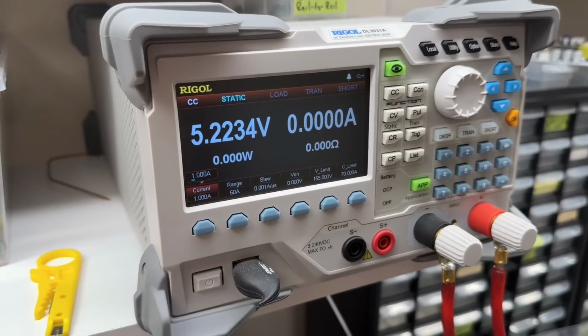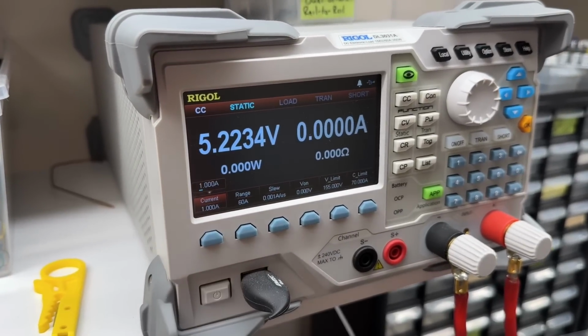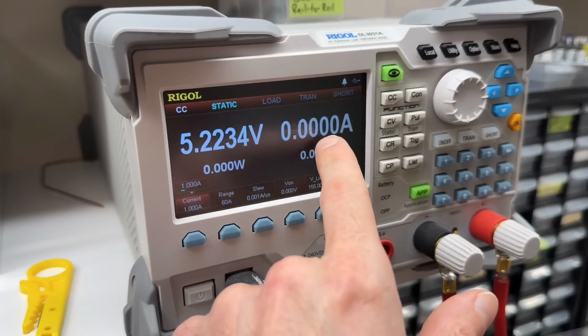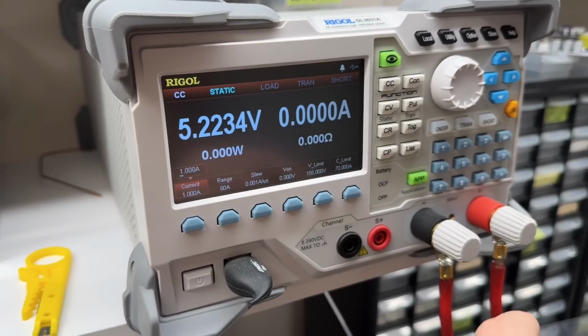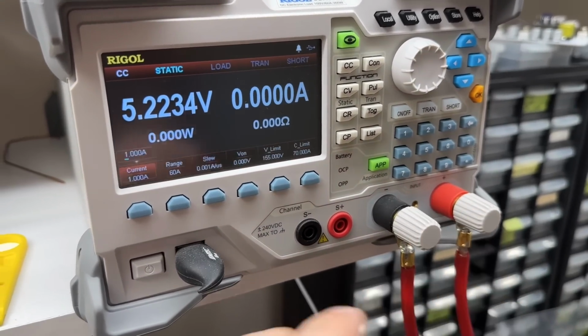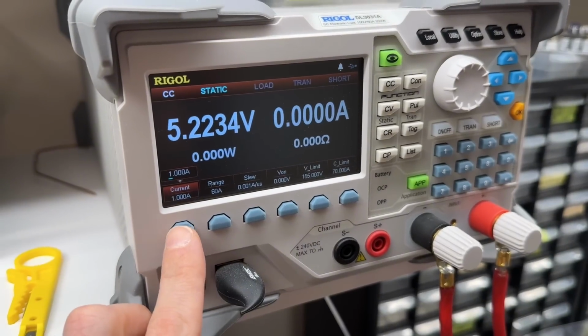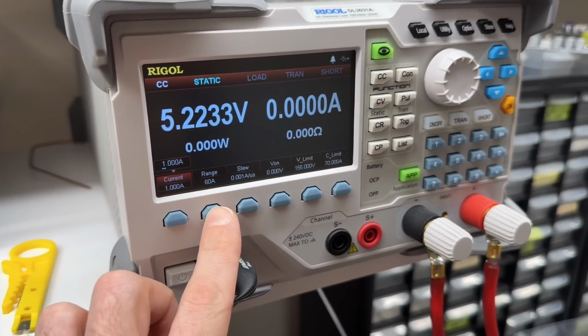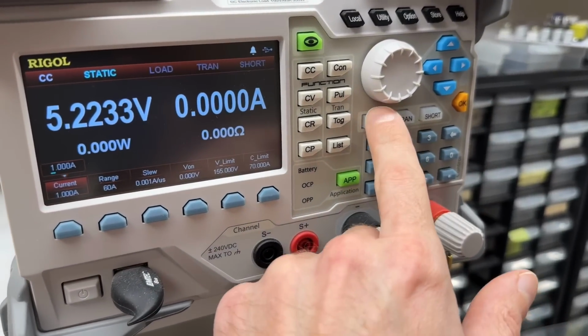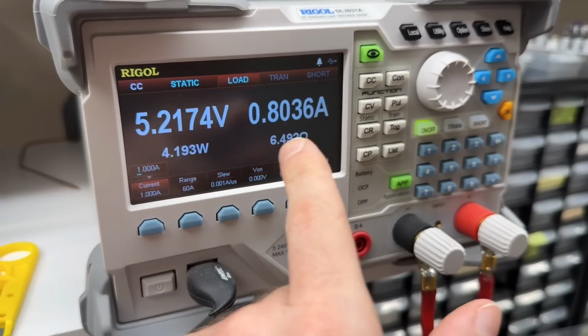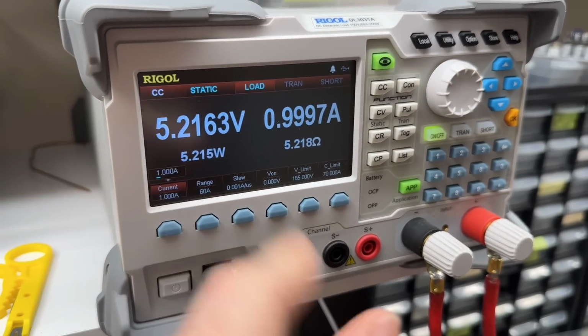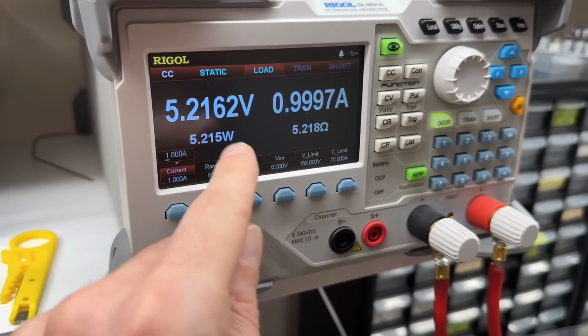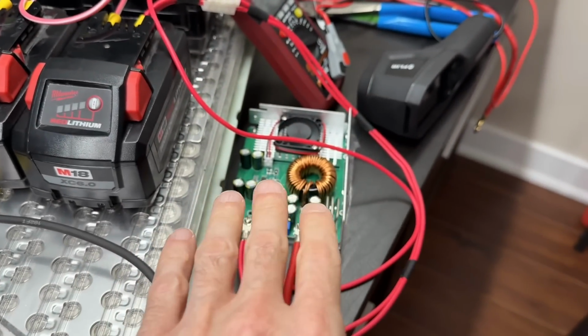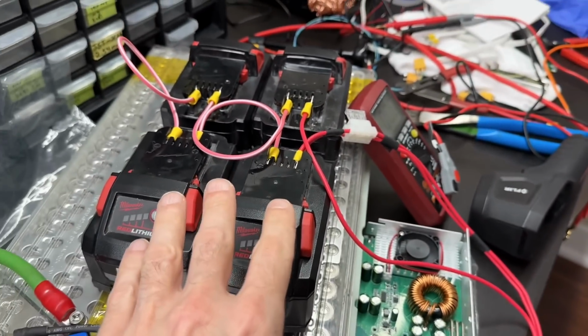Looking at the electronic load, we have 5.2 volts and the load isn't turned on, so we're not drawing any amperage right now. This is basically an open circuit. On the current scale, we're in the range of 60 amps. We can turn on the load, and now we're pulling 1 amp at 5 volts, approximately 5 watts. We're using 5 watts of the capacity of this converter, and it's all coming from these batteries.